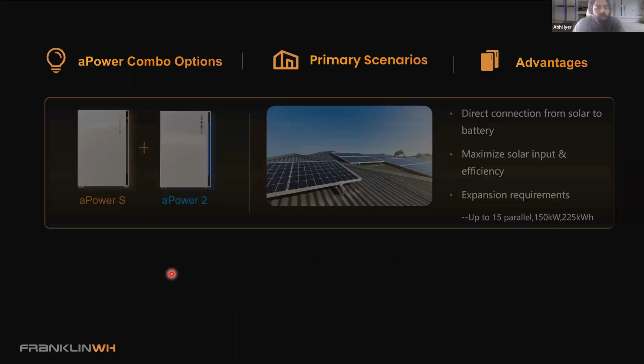However, the most common use case scenario, especially since an average system size in both the US and Canada varies between 10 to 12 kW of PV AC, is that you'll land all of that PV on the aPower S, which is then AC coupled with the aPower 2 unit. The magic of this combination gives you access to 21.5 kW of total continuous power output from those two batteries combined, and a total of 30 kWh of energy capacity.